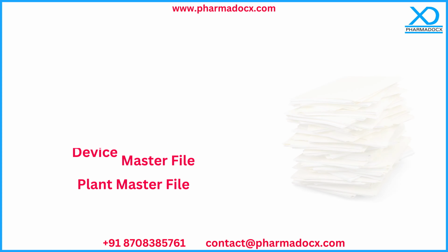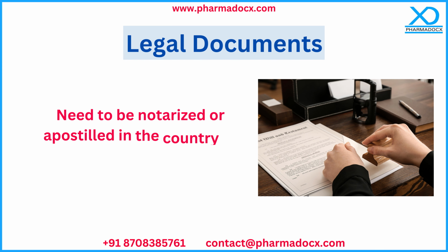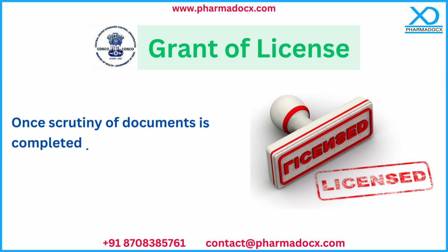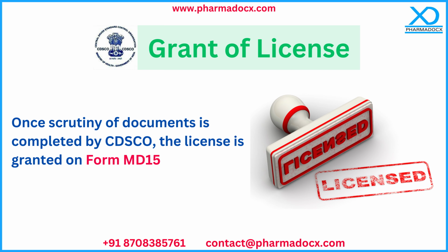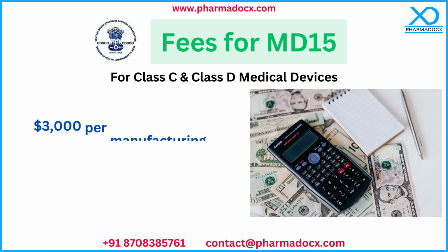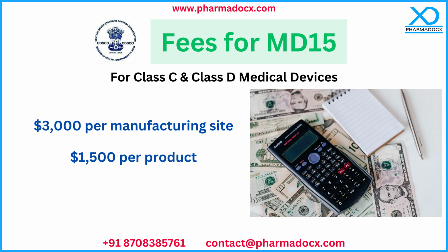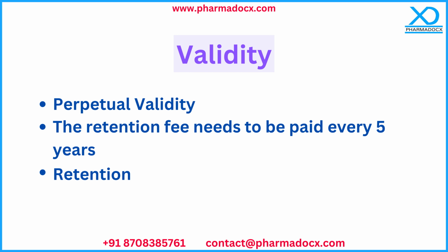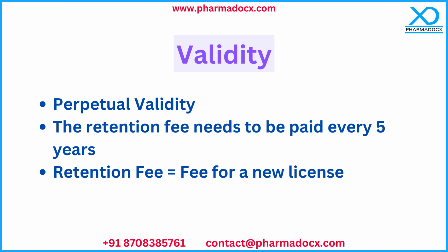The legal documents which will be uploaded on the CDSCO portal need to be notarized or apostilled in the country of origin. Once the scrutiny of documents is completed by the medical device officers at the CDSCO headquarters in New Delhi, the license is issued to the firm on Form MD15. The fee for Class C and Class D medical devices for import is $3,000 per manufacturing site and $1,500 per product. This license is also valid in perpetuity, subject to a payment of retention fees every 5 years, which is calculated the same as that of a new import license.